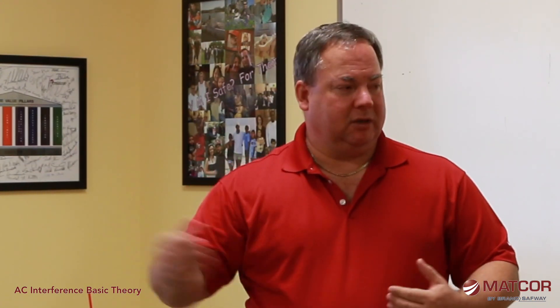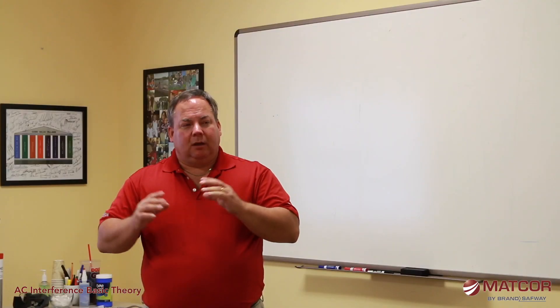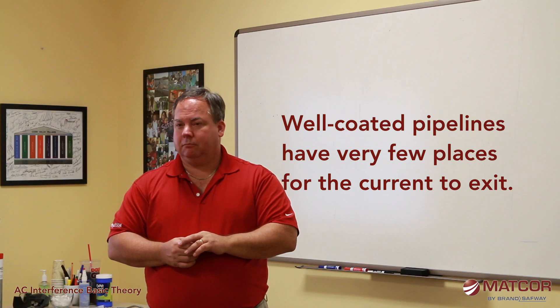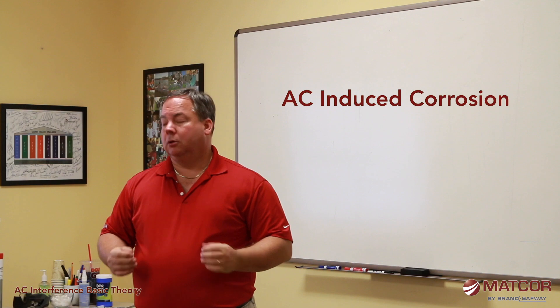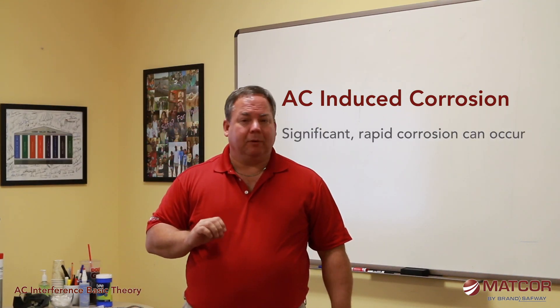AC induced corrosion is the effect that occurs when the pipeline picks up this AC current. The AC gets on the pipeline and has to leave at some point — it can't just stay on the pipeline. So this induced AC is going to dissipate back to earth, and eventually back to the grounding system of the substation of the AC transmission facility. With well-coated pipelines, there are very few places for that current to exit, and that's where AC induced corrosion starts.